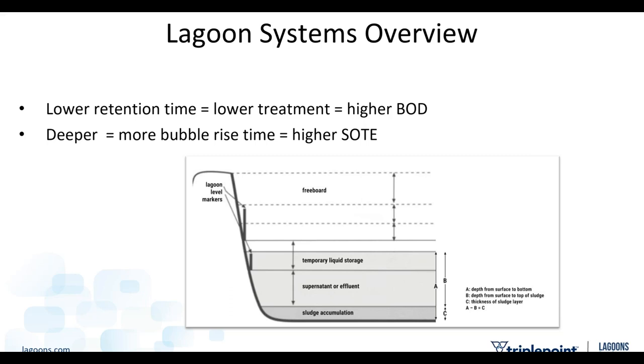But just know that the sludge accumulation that you see at the bottom of your pond, that's yielding lower retention time. Consequently, you're getting less treatment, and you're going to see higher BOD, higher biochemical oxygen demand in your effluent. As you go deeper, you get more bubble rise time, and that leads to a greater oxygen transfer efficiency. Standard oxygen transfer efficiency is the acronym on the screen.